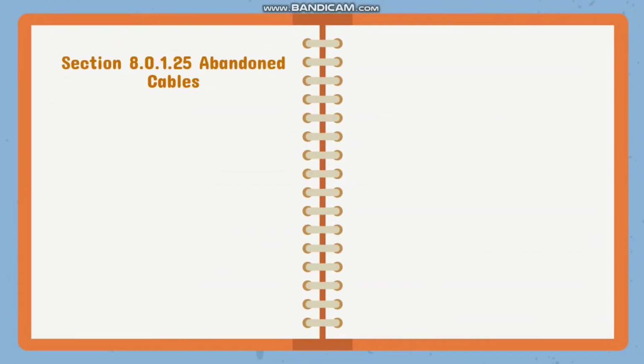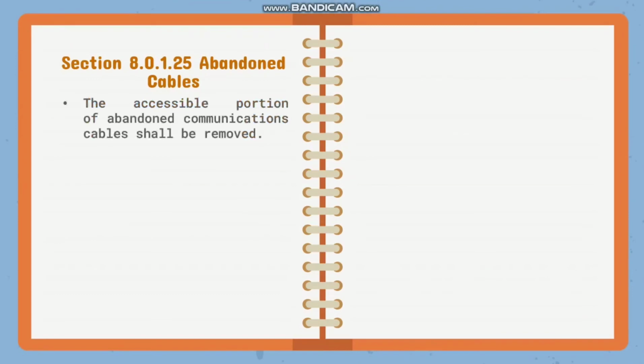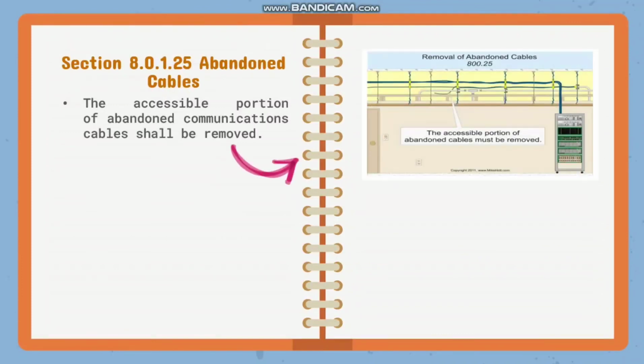Next section naman po is Section 8.0.1.25, abandoned cables. Abandoned cable po is a cable that isn't terminated to equipment or is not identified for future use with a tag. So ito po yung mga cables na hindi na kailangan o hindi na ginagamit and are just left in place. So according po dito, the accessible portion of abandoned communications cable shall be removed. So kailangan po siyang tanggalin para po ma-reduce yung risk ng electrical fire.